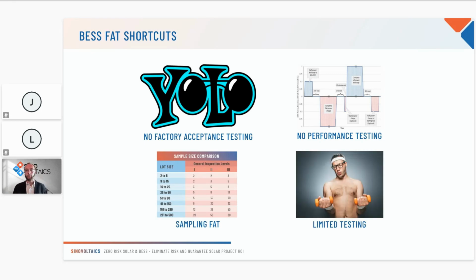Last but not least, limited testing. This happens during the performance testing. I took this picture to illustrate it, because I found it a nice way to explain it. It's like when you do performance testing, it's much easier to lift a small weight than to lift a really big weight. In other words, for the battery business, it's much easier to test at 10% of the power output of your BESS than to test at full power output. For example, if you have a 5 megawatt-hour BESS, some suppliers will only agree to test at 1 megawatt power output. So of course, it's much easier to pass any thermal test, safety test, or BMS control test if you test at 1 megawatt instead of the full 5 megawatts.